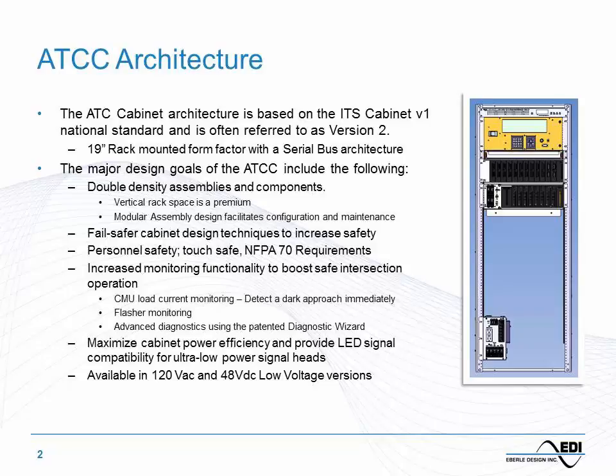These cabinets are designed to increase technician safety and motorist safety — touch safe, low voltage, reduced technician protective equipment requirements. We've also added state-of-the-art technology improvements. For example, the cabinet now has load current monitoring, so when a vehicle approach goes dark — maybe the field wire just got cut — we detect that immediately. That's a safety enhancement. We also monitor the flashers.